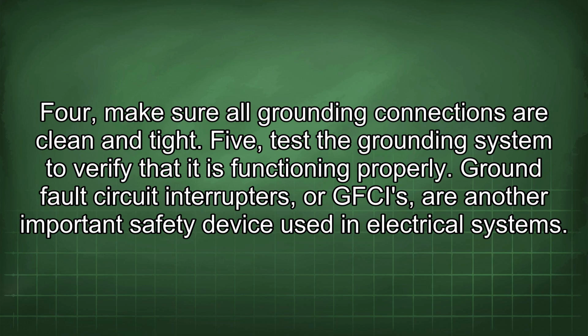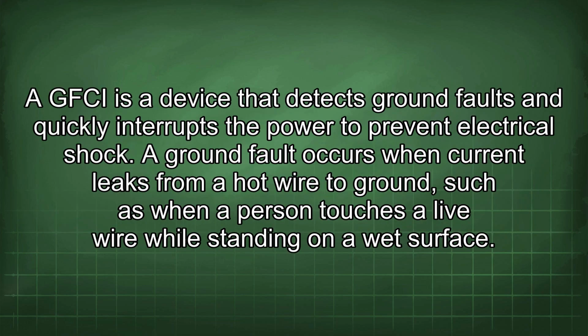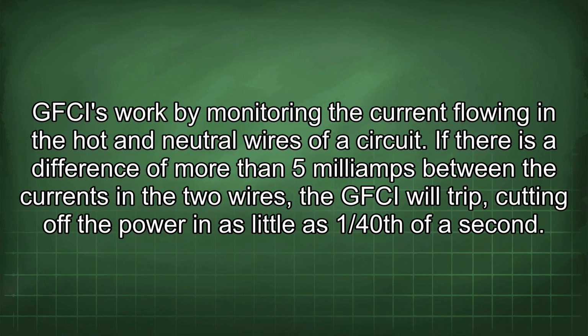Ground fault circuit interrupters, or GFCIs, are another important safety device used in electrical systems. A GFCI is a device that detects ground faults and quickly interrupts the power to prevent electrical shock. A ground fault occurs when current leaks from a hot wire to ground, such as when a person touches a live wire while standing on a wet surface. GFCIs work by monitoring the current flowing in the hot and neutral wires of a circuit. If there is a difference of more than 5 mA between the currents in the two wires, the GFCI will trip, cutting off the power in as little as 1/40th of a second.